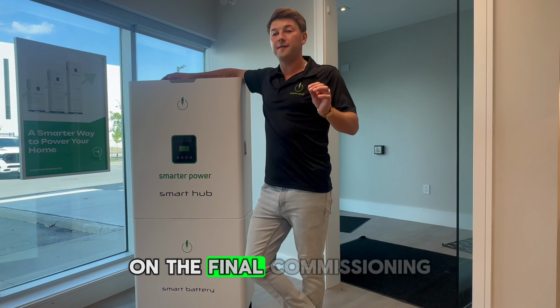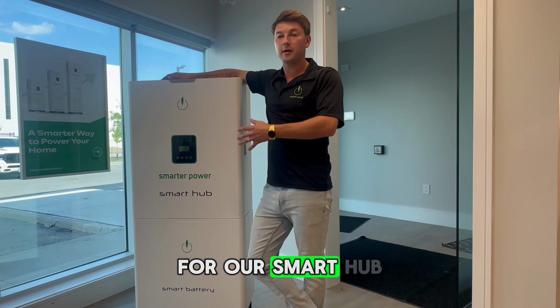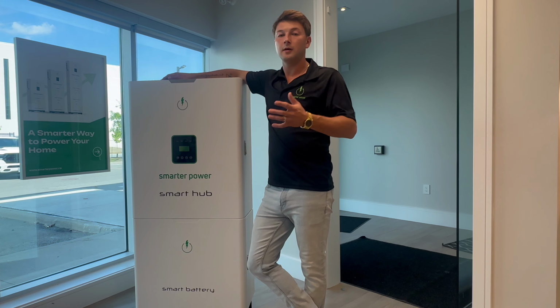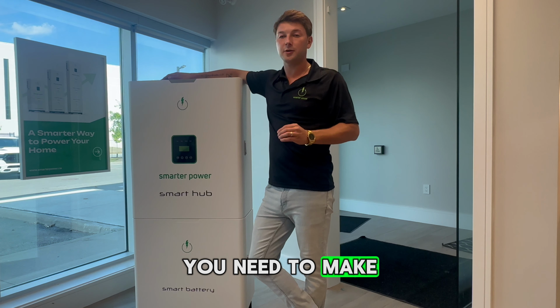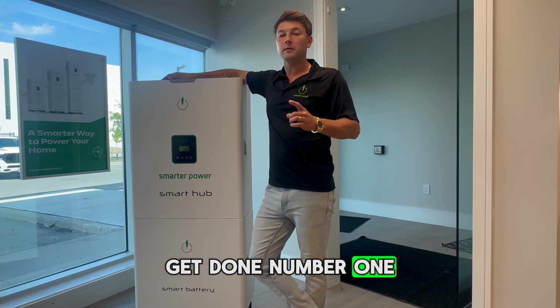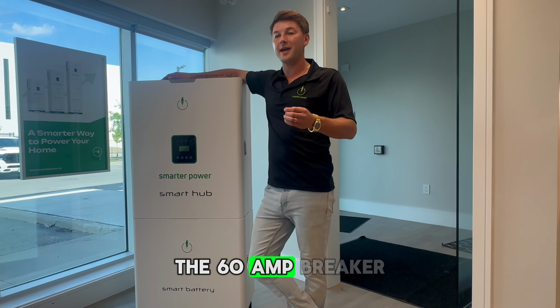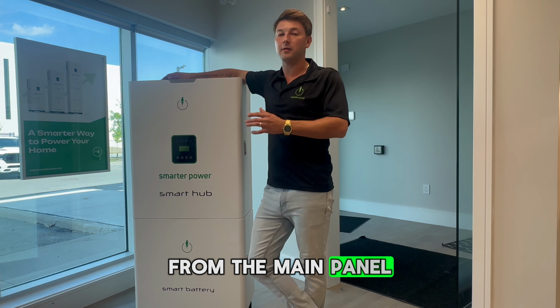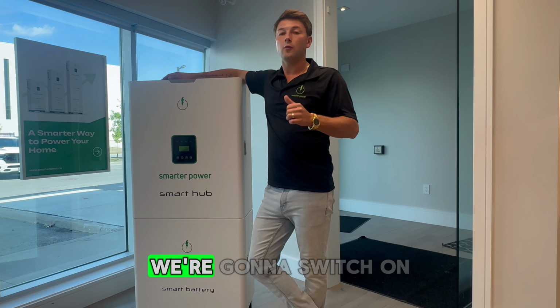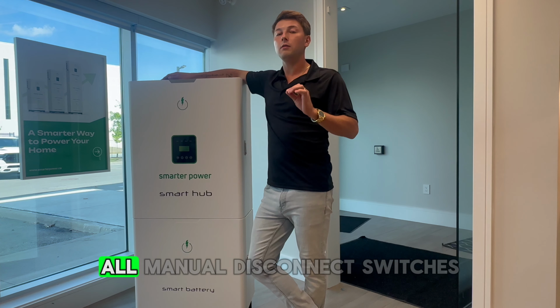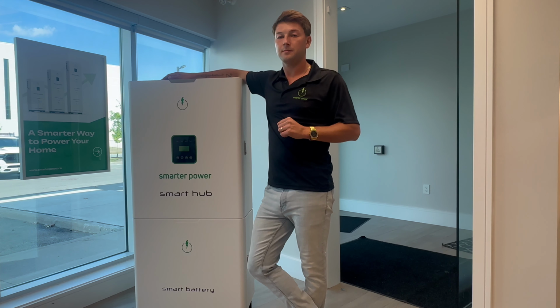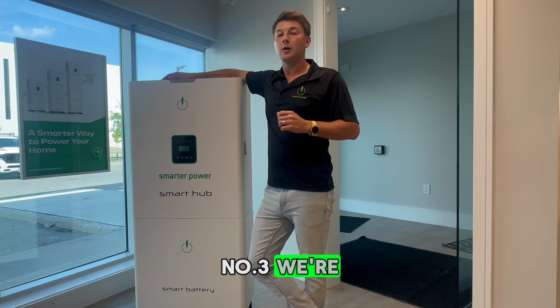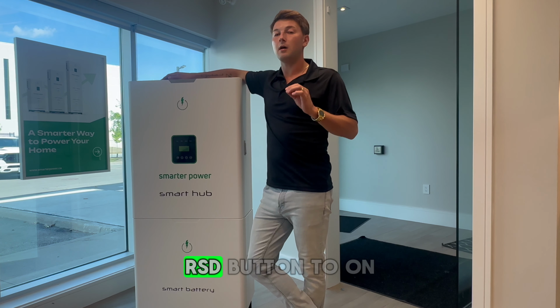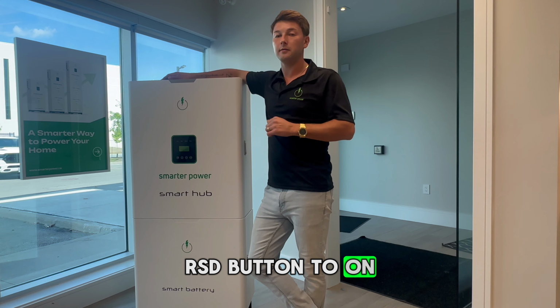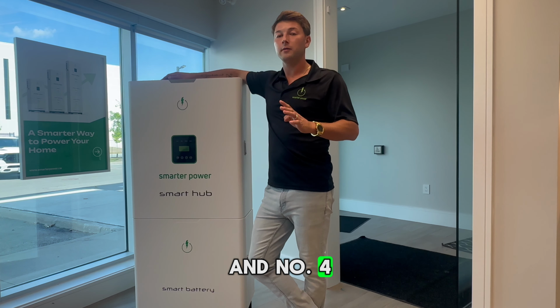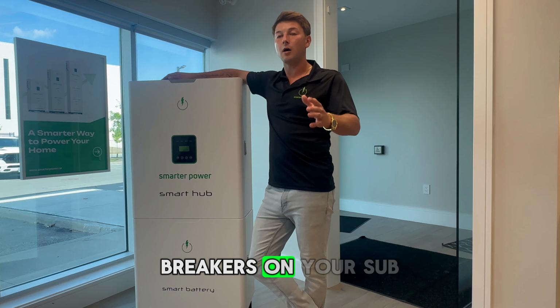Hey guys, we're now in the final commissioning steps for our Smart Hub battery system. We're going to go through a few things that you need to make sure get done. Number 1 is we're going to switch on the 60 amp breaker from the main panel. Number 2, we're going to switch on all manual disconnect switches. Number 3, we're going to push the Smart Hub's RSD button to on. And number 4, we're going to switch on breakers on your sub panel.